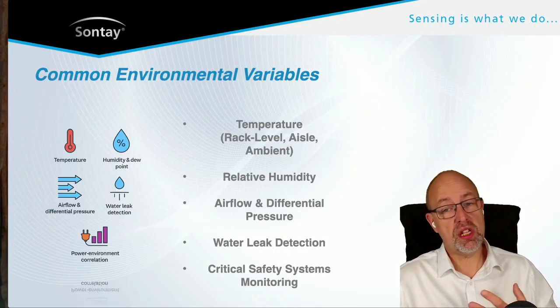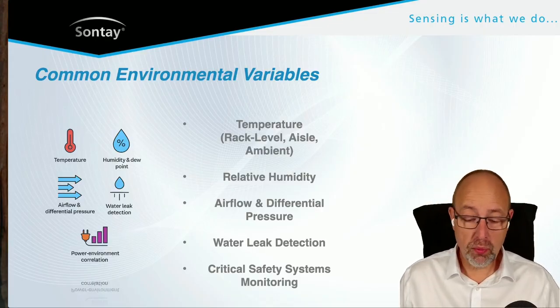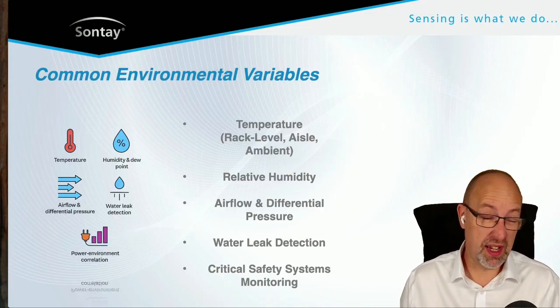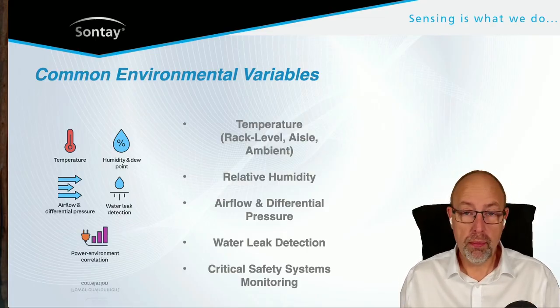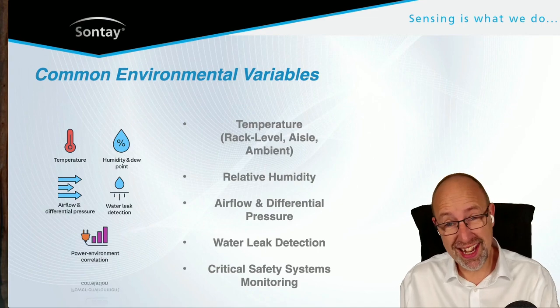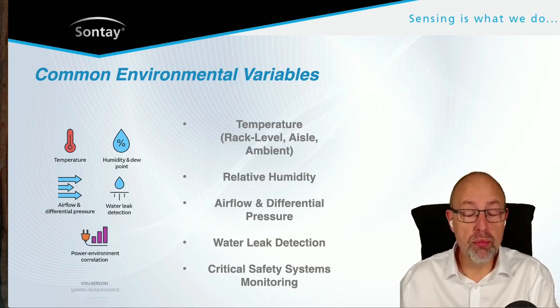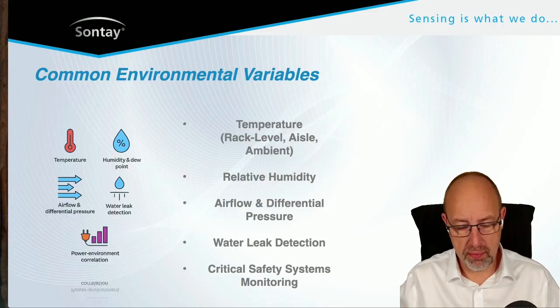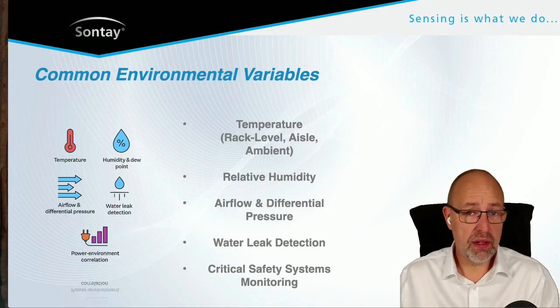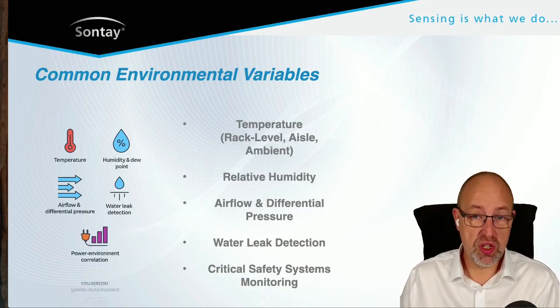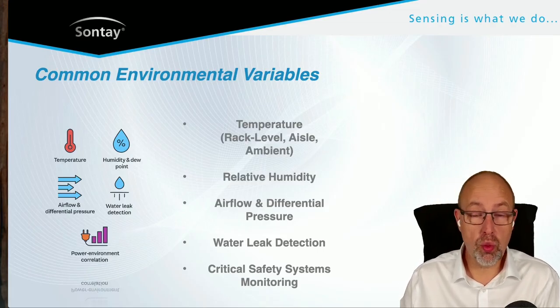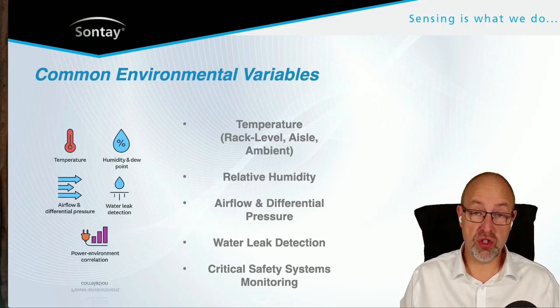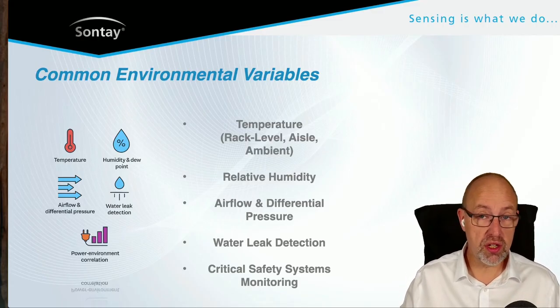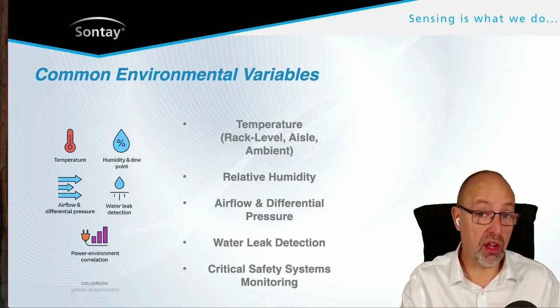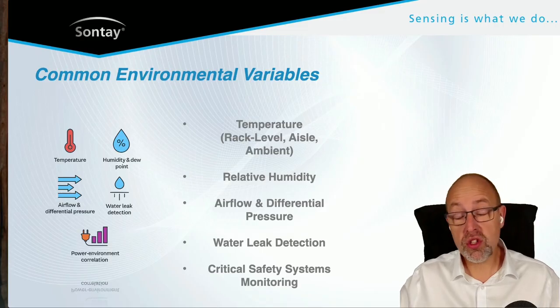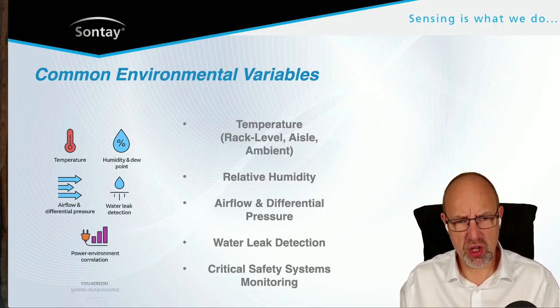Things that we monitor within a data center. The main one is temperature. There is a lot of temperature sensing. That's true of all environmental monitoring everywhere, but temperature is a key thing, because servers generate a huge amount of heat, and of course we need to remove that heat from the data center. Otherwise everything's going to overheat, it's going to melt down. We need to do that in a lot of ways. We've got the rack, aisle and ambient temperatures here. So that's looking at air temperatures, but of course chilled water temperatures need to be monitored closely, as well as things like condenser water temperatures, where you've got chillers in your building. That will have a condenser, or is likely to have a condenser water system, which is going up to cooling towers. So all of that needs to be managed as well. So temperature is a huge part of this.